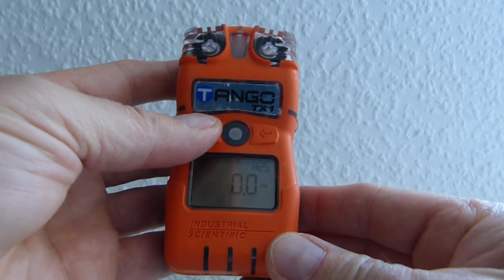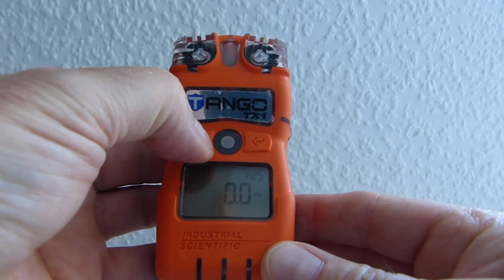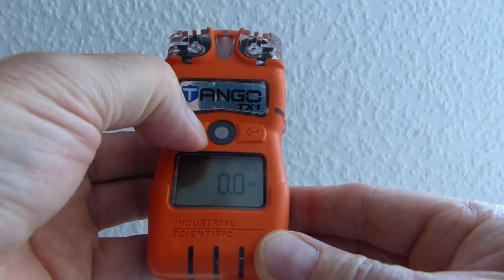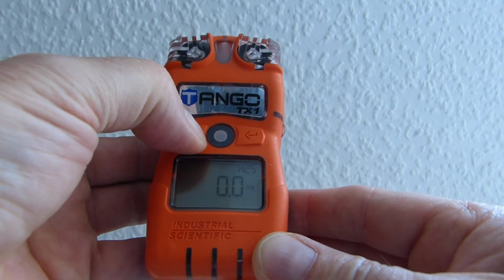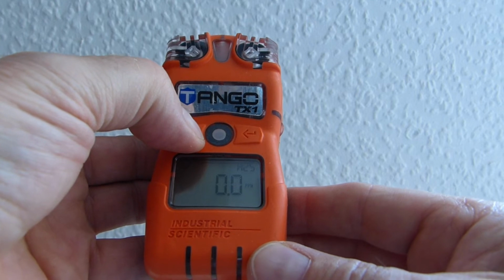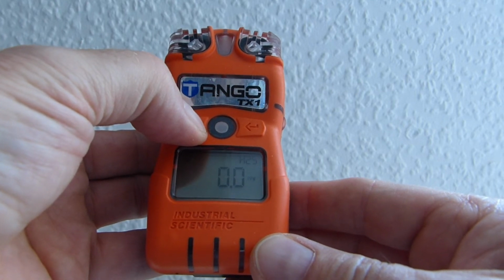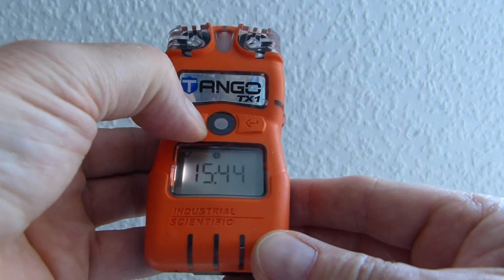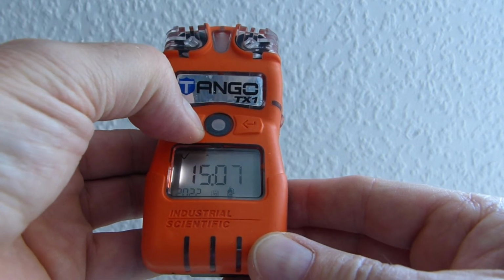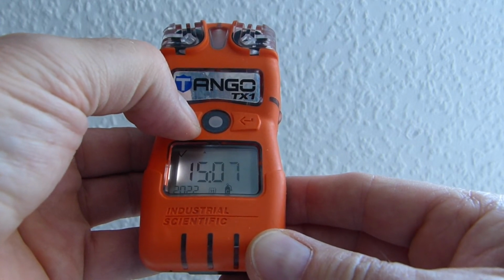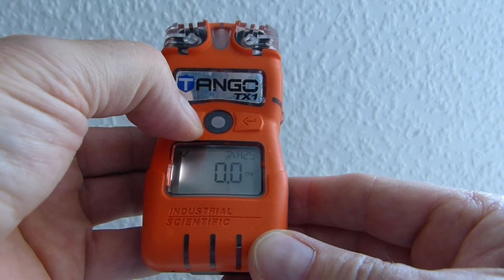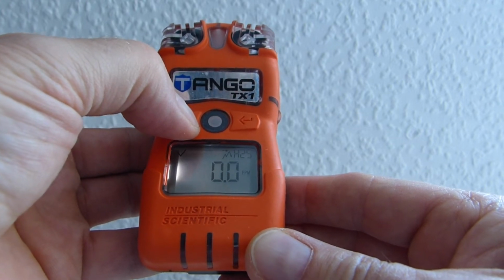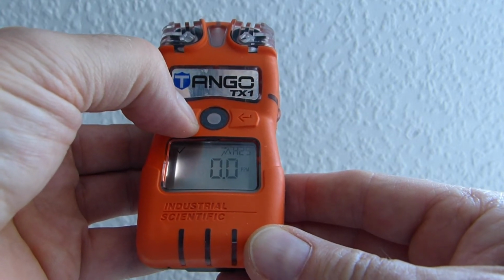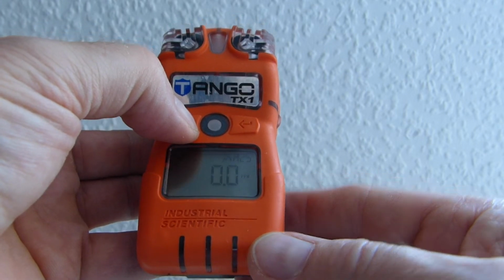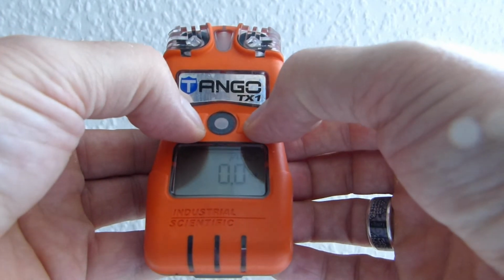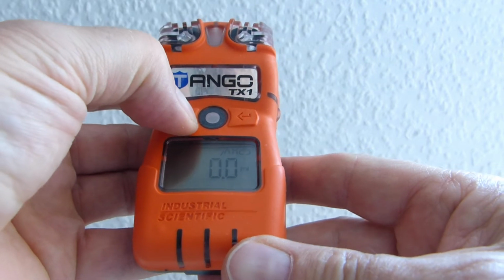During operations of the Tango TX1, you can use the left button to toggle the screens. This is the standard reading screen where you can see the readings of the actual gas monitoring. The next one is indicating the time. The next one is indicating the next calibration date. The next one is the peak, so basically the highest reading you have had over a given period of time. In order to clear it, you press and hold the right button.